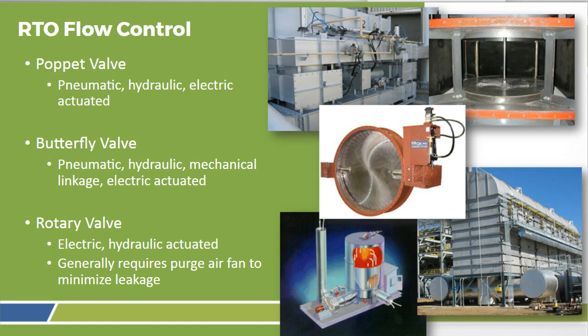But these can all be pneumatic, hydraulic, electrical. I mean, pretty much you name it. Additionally, the rotary valve, same thing. It generally requires a purge air fan to kind of block and bleed in a way that the seal all around the entire valve. So, but it works. You have air coming in through the bottom generally. It goes up into the combustion chamber and then down again. So it works like any other thermal oxidizer, or RTO, I should say.